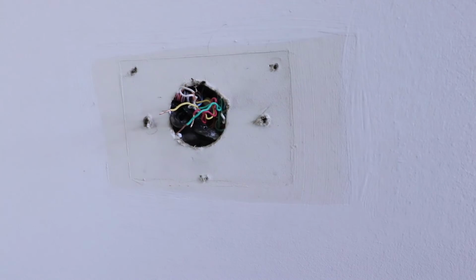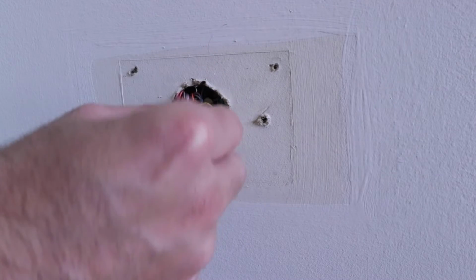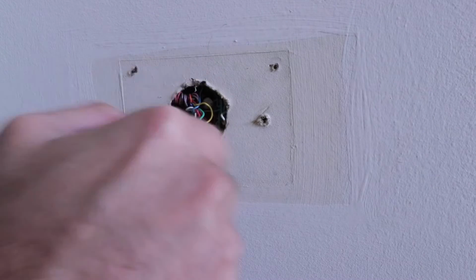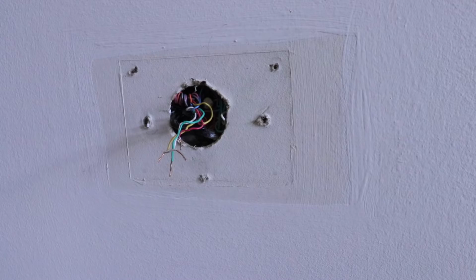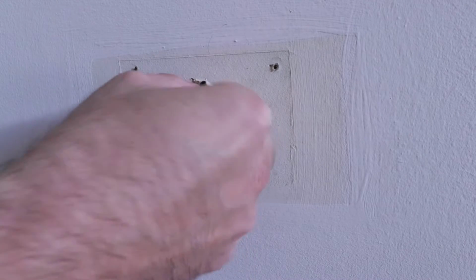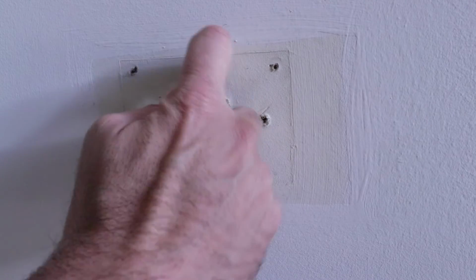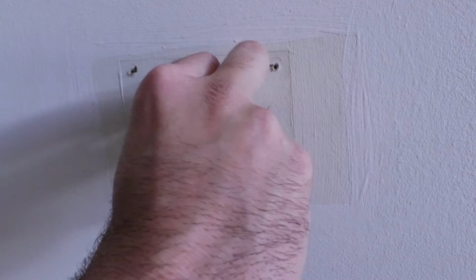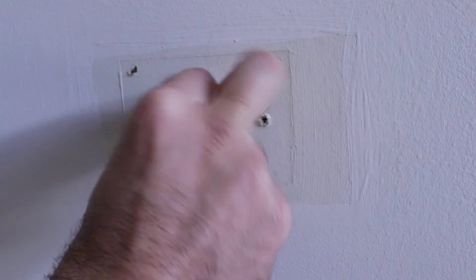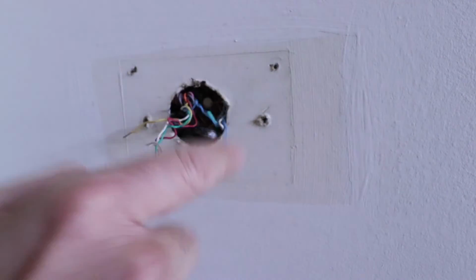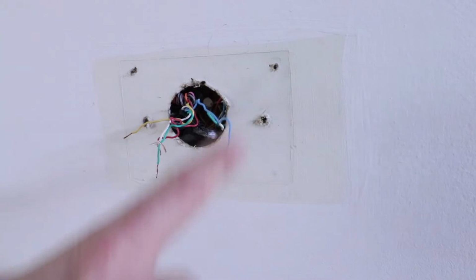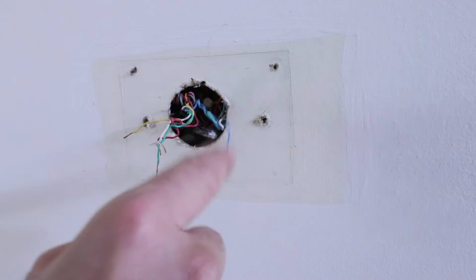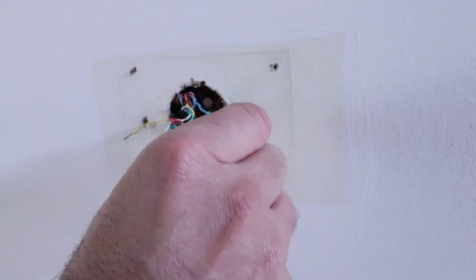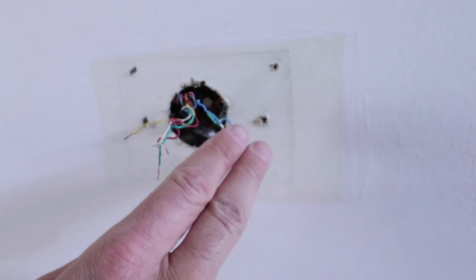Now that we've got the thermostat removed, we can see some of the wiring in the wall, and identify some extra wires. We've got an extra blue wire connected to the same bundle, so we could actually use this as a common wire because it goes down to our HVAC system, but we'd still need to connect that to the C terminal down there.